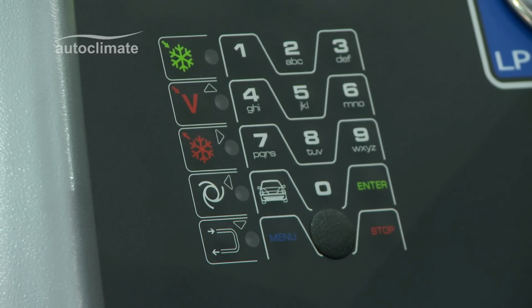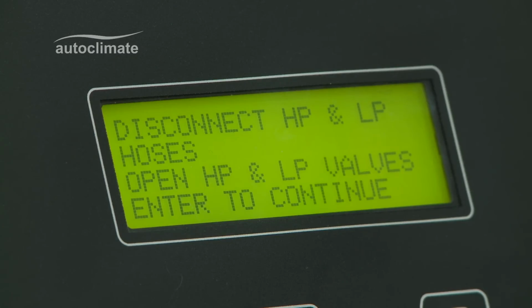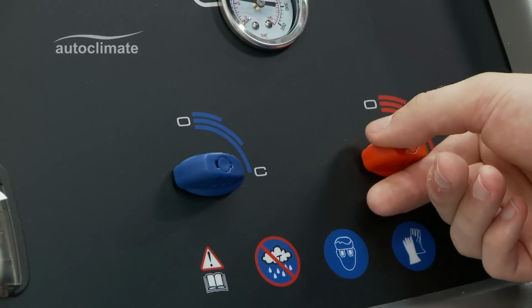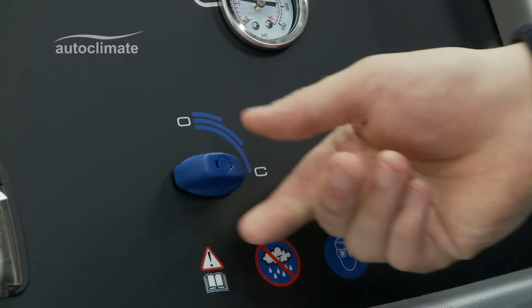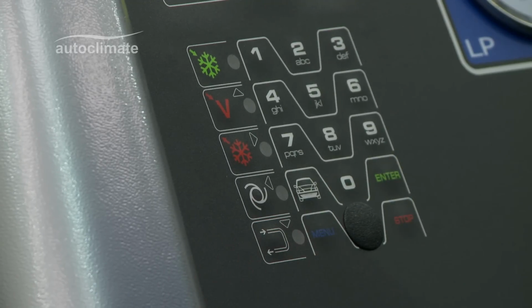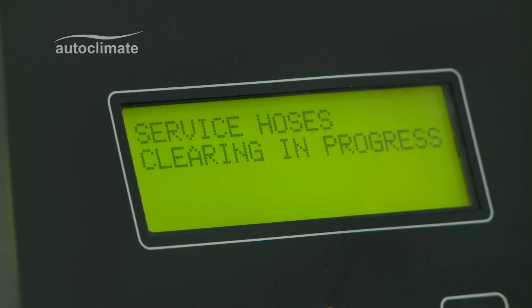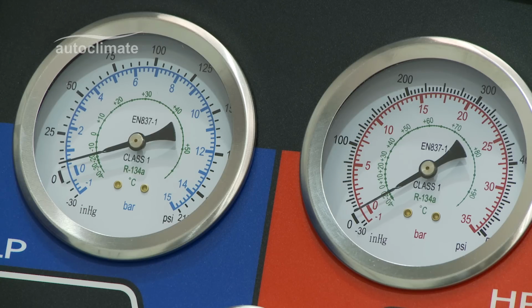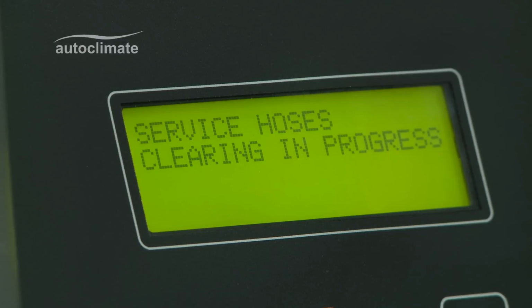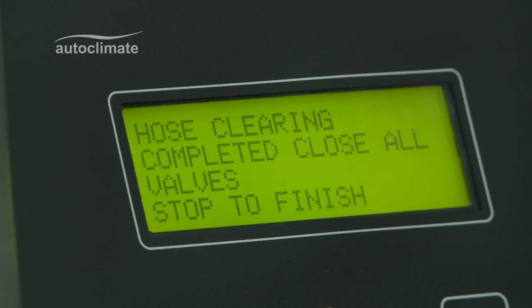Although it may have been carried out, a prompt shows to disconnect the service couplers from the vehicle. Open the high and low pressure panel valves and press Enter to continue. The display shows service hoses clearing in progress. This recovers the refrigerant from the hoses. The high and low side pressures drop to zero. Confirmation that the process is complete is displayed.